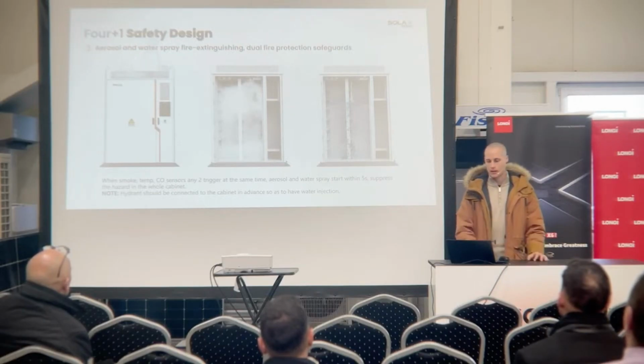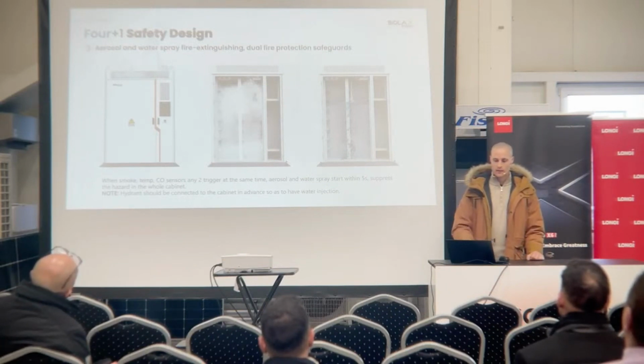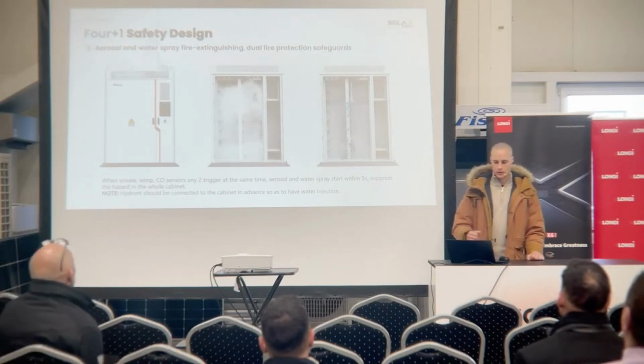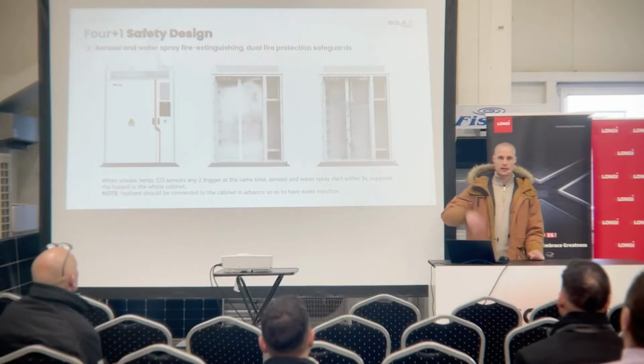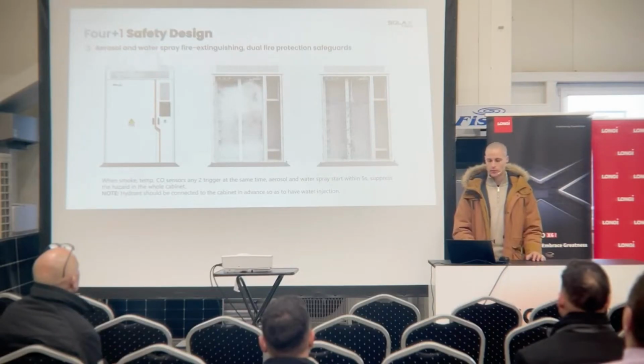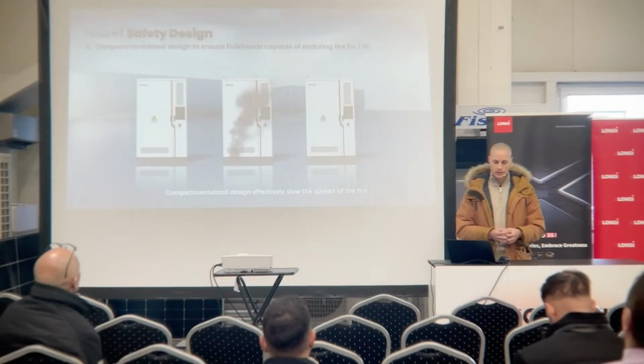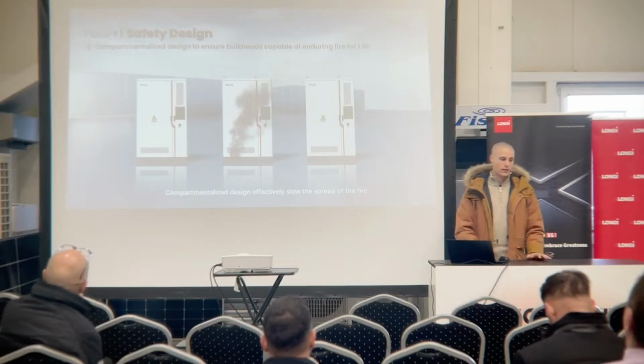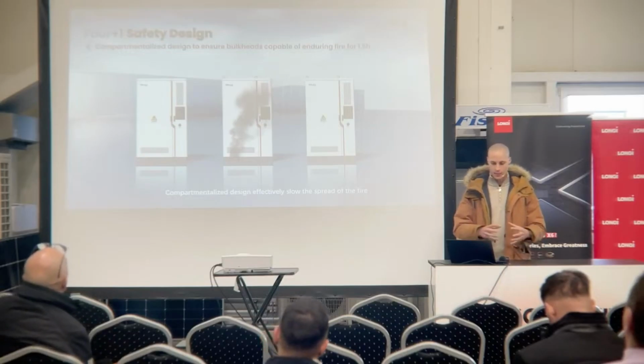And if it's still not enough, the first is the aerosol that goes into the cabinet, and then if you have the fire water connected to the cabinet, it can flood the whole cabinet with water in case, just to stop the fire. And if it's still not enough, then the whole cabinet is designed to withstand the fire for 1.5 hours. So it's the time that you have to call the firefighters to suppress the fire. So this is the last step of the fire prevention mechanism.